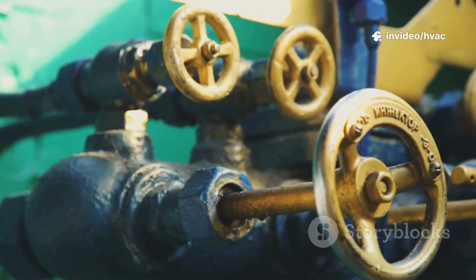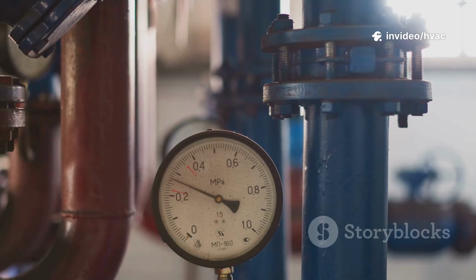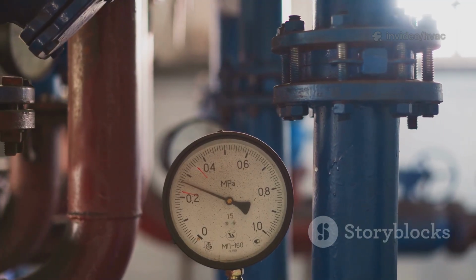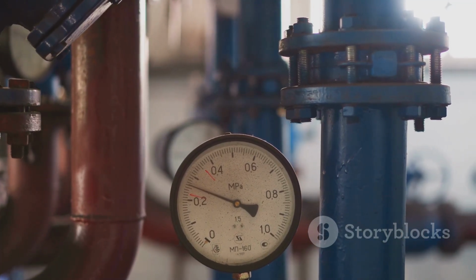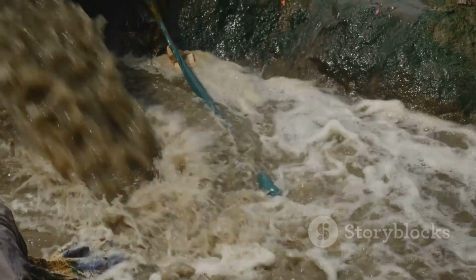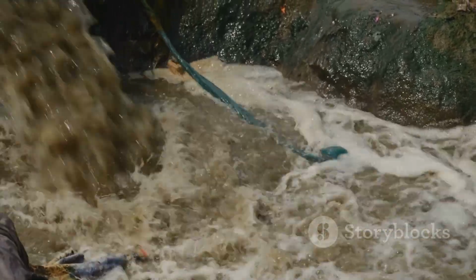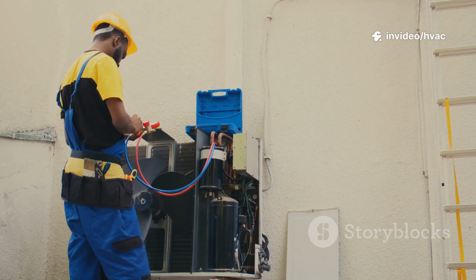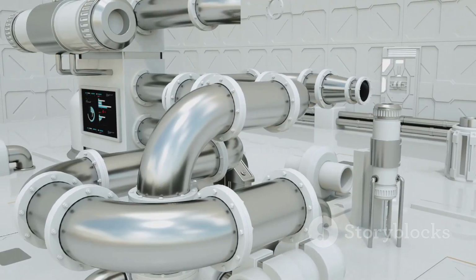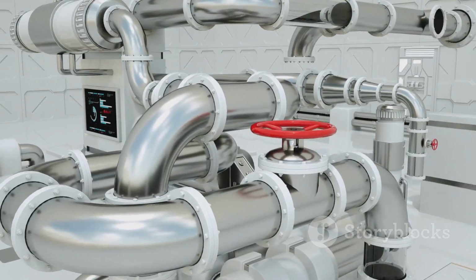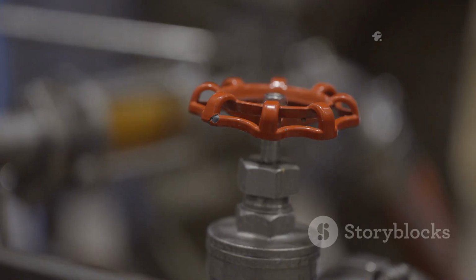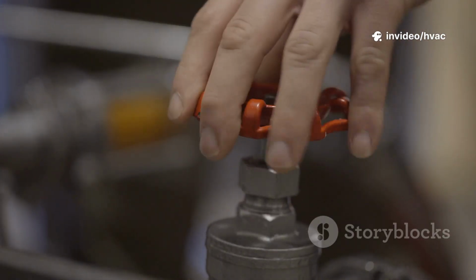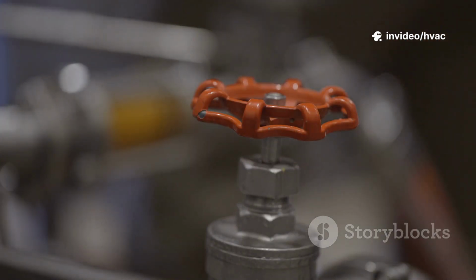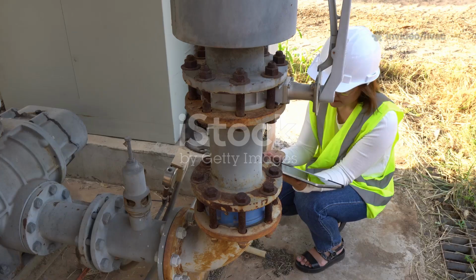A traditional two-way valve has no internal pressure regulator. Its flow rate is completely dependent on two things: its percentage of opening and the pressure difference across it. If the system pressure fluctuates, the flow through a traditional valve will also fluctuate, even if the actuator has not moved at all. This creates an unstable and inefficient system. A PICV, by separating the function of pressure regulation from the function of flow control, solves this problem entirely. The actuator controls the flow based on temperature needs, and the internal mechanics handle all the pressure variations automatically, ensuring stable and precise performance at all times.